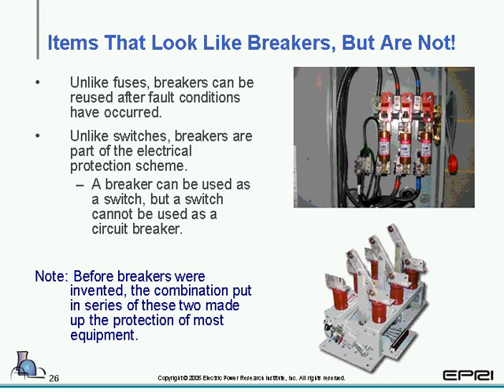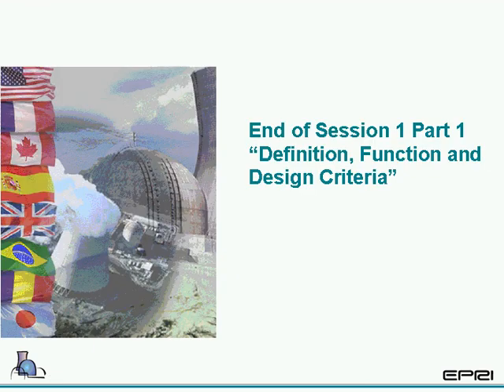Unlike fuses, breakers can be reused after a fault condition has occurred. And unlike switches, breakers are part of the electrical protection scheme. Breakers can be used as switches, but switches cannot be used as breakers. And just as a note, before circuit breakers were invented, these two items, the fuse and the switch, were put in series with one another for most protection of equipment.